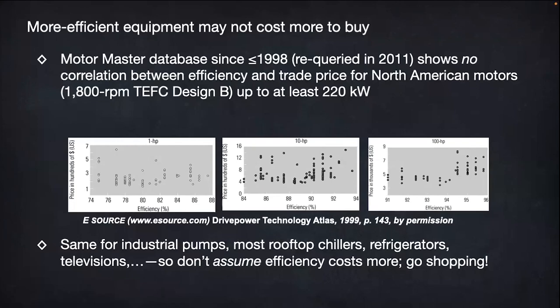When we last called up the Motor Master Plus team 11 years ago, standards had already knocked the worst motors off the market, so the modelers assumed we were all done. They didn't want to bother requerying their model, but they humored us and did so anyway. They were astonished to find there was still no correlation between efficiency and price for common motor types up to at least 300 horsepower.